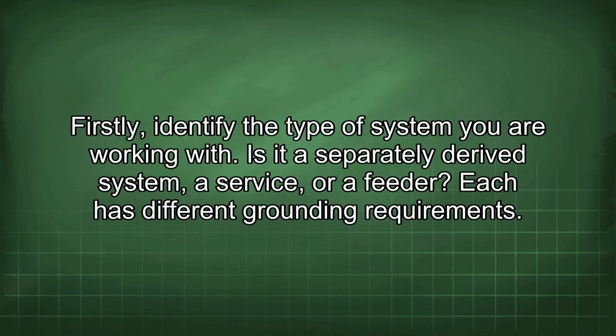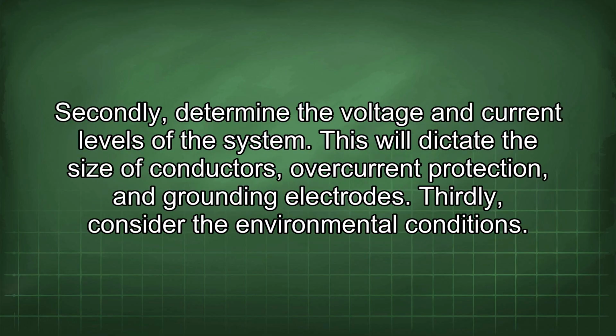Firstly, identify the type of system you are working with. Is it a separately derived system, a service, or a feeder? Each has different grounding requirements. Secondly, determine the voltage and current levels of the system. This will dictate the size of conductors, overcurrent protection, and grounding electrodes.